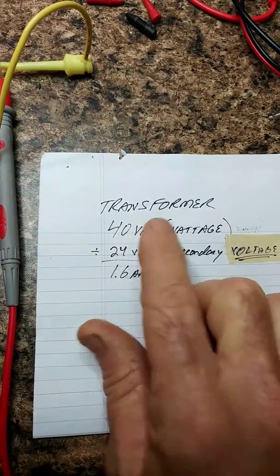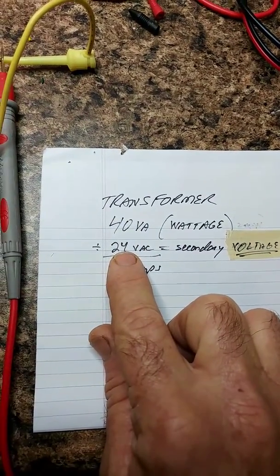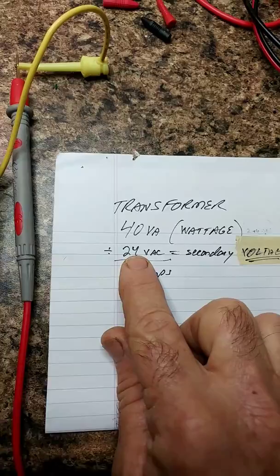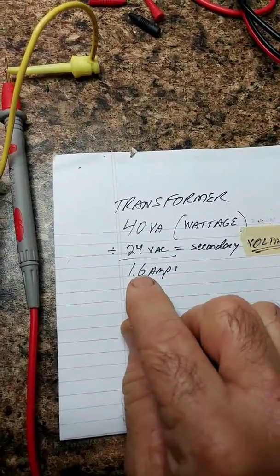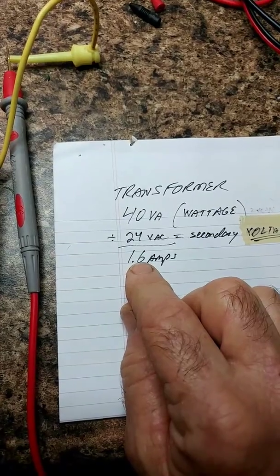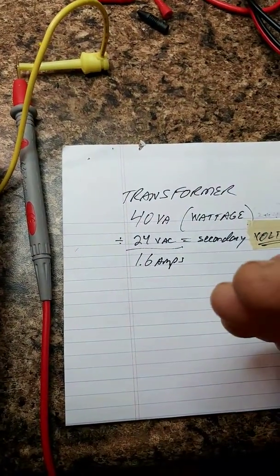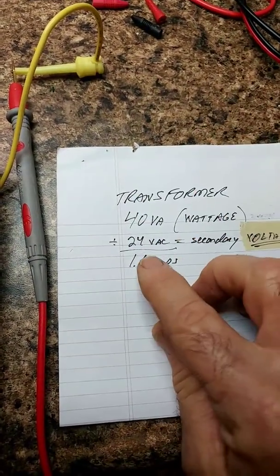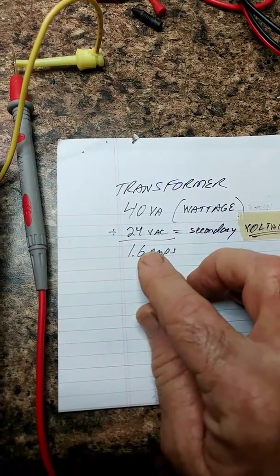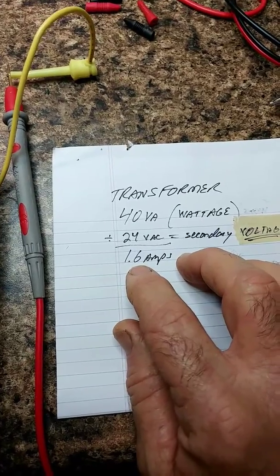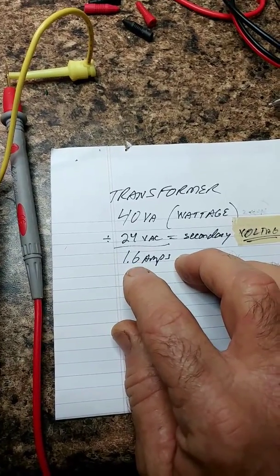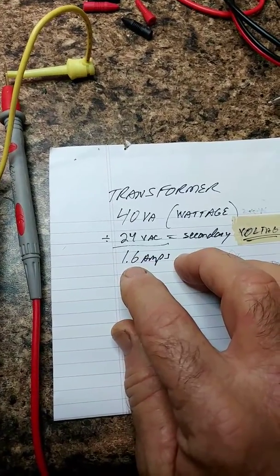So a 40VA transformer, if you divide the secondary voltage into it, which is 24 volts, in our case it's 28, it's rated for 1.6 amps. So if I'm using 28 volts, it would actually be less than 1.6 amps. So it doesn't take a lot of amperage to burn up a 40VA transformer.